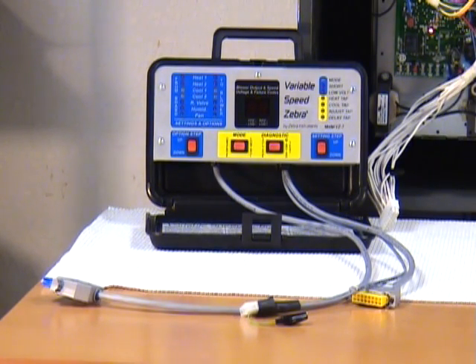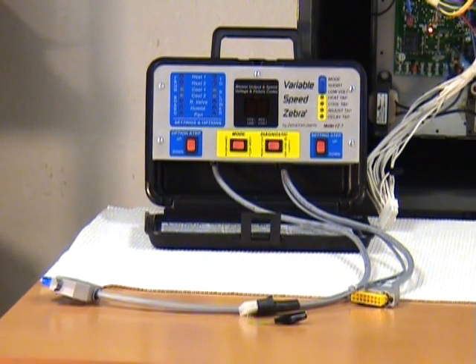While we know of no other connectors that match those connectors on the HVAC blowers, don't exceed that voltage by trying to modify them. Carefully plug the connectors into their mating connectors. The pins on those 16-pin plugs are delicate. We didn't choose them, the motor manufacturer did, but we have to be able to match them. Those pins will break or bend if you force them. Gently wiggle those connectors together, and if they don't go together for some reason, don't push. Figure out why. For those of you guys that ignore this, we do offer replacement harnesses for the variable speed zebra.